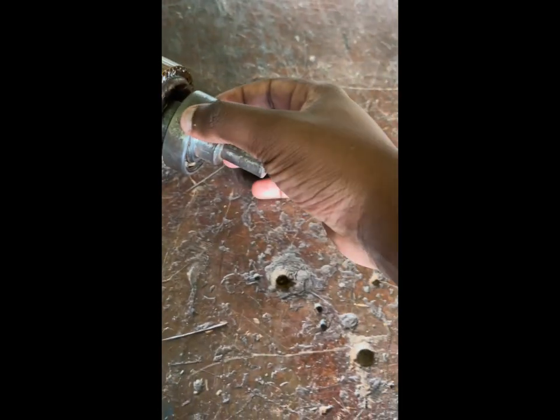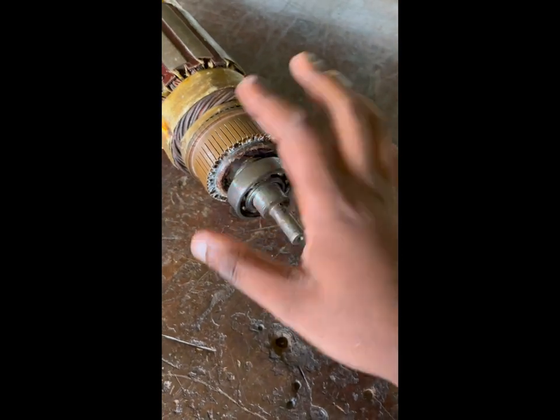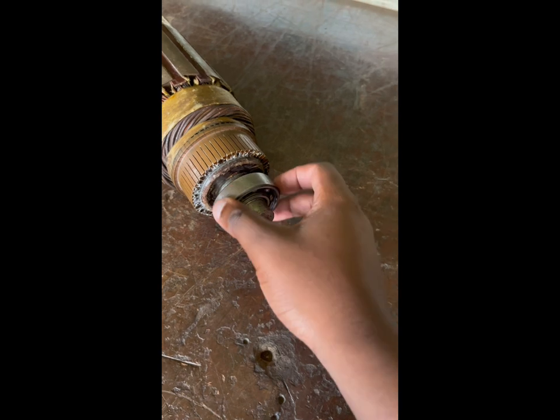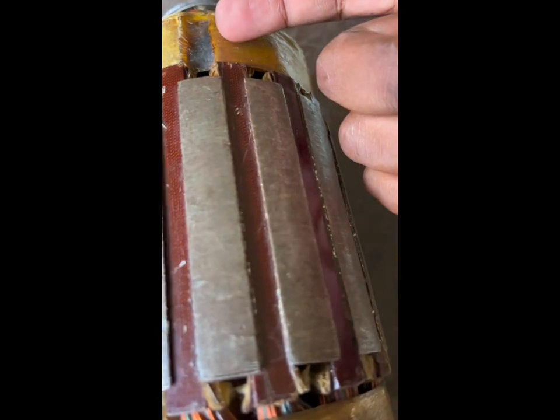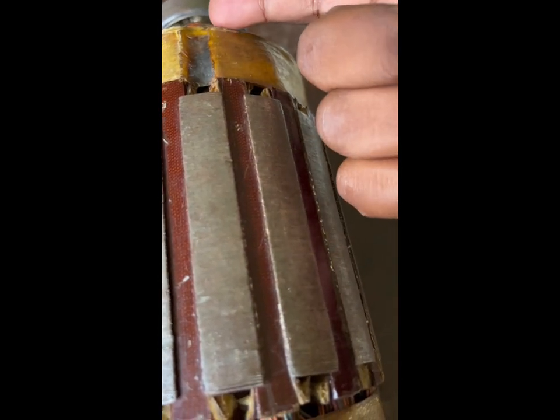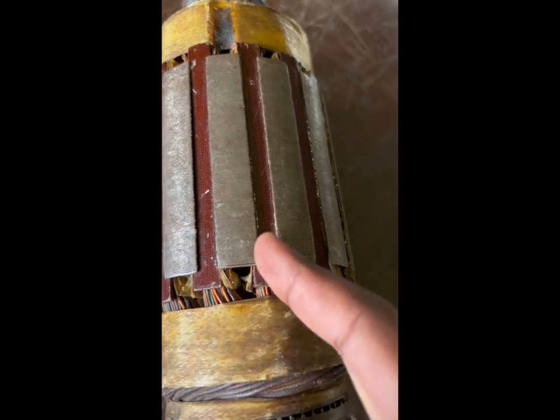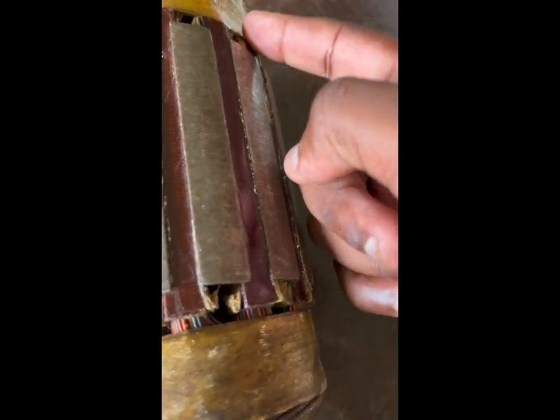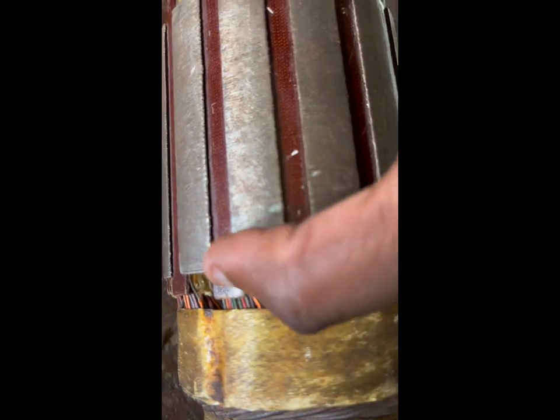Then if we look again, on each side we have bearings so that it rotates smoothly. Here is my other side bearing. This is our shaft. Then again there is the core, which consists of armature conductors that go into slots in the armature core. And you can see that this armature core is made of sheets which are insulated from each other.